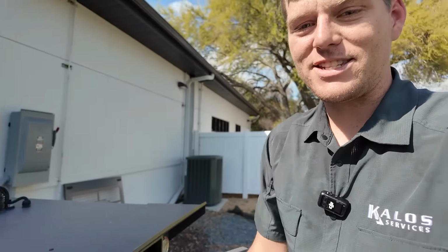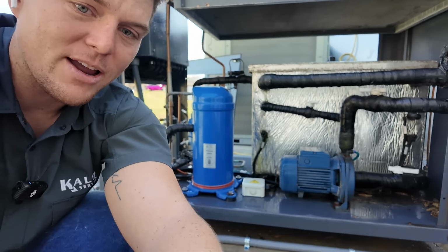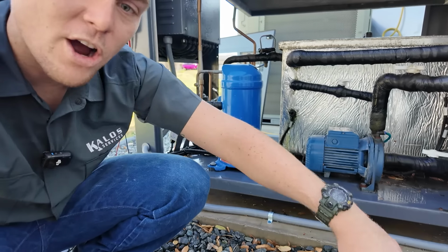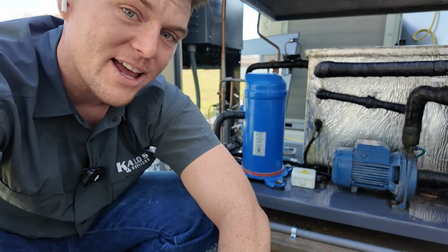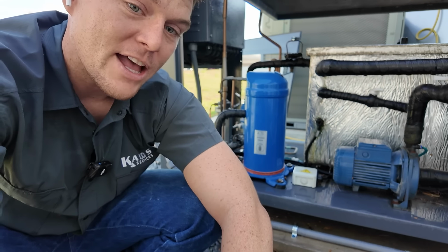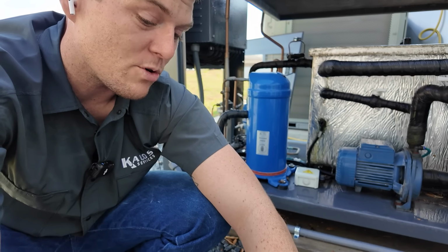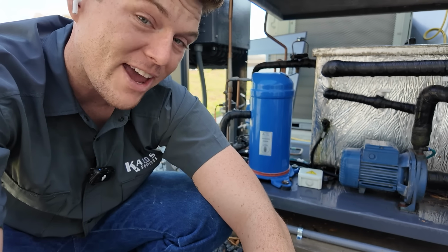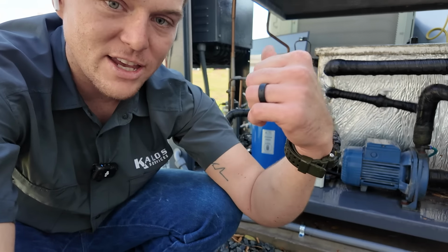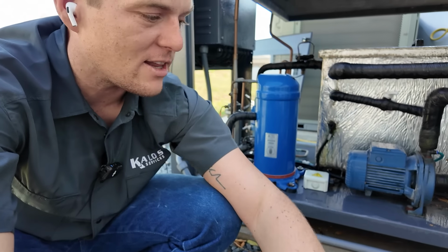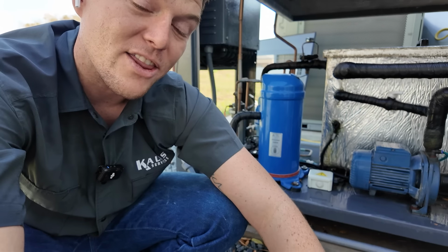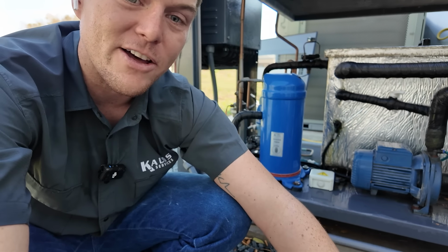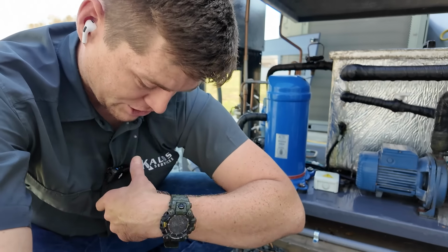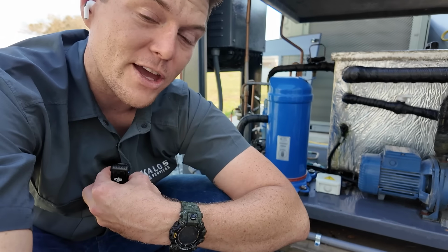Now, the issue with this system is that it tripped on a few different things. Tripped on the water pump. It's down here in the bottom, right? Now, this is a 400 volt unit made in Germany at 50 hertz. And so this water pump is actually pulling somewhere close to 3.25 amps, which is enough to trigger the outdoor board to tell it, hey, amp draw is high. Now, the bearings in this motor don't sound the best, and I found out from the client that this system has actually been sitting for a couple years after they ran it for a year.